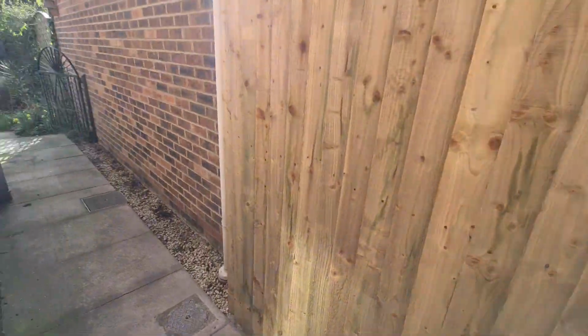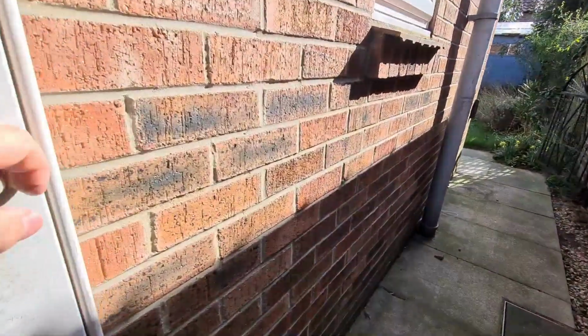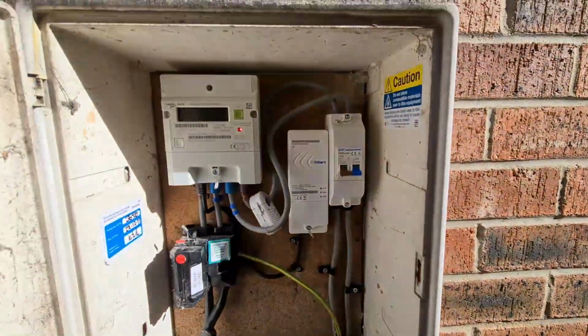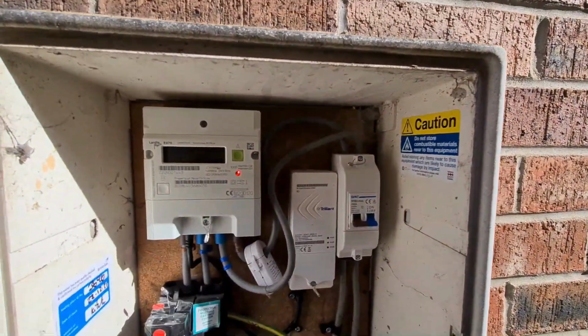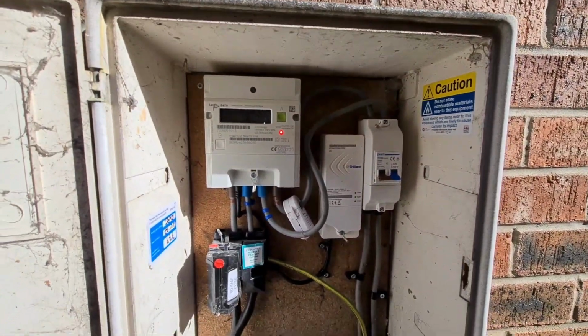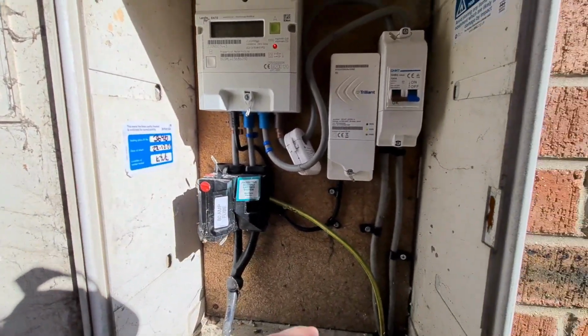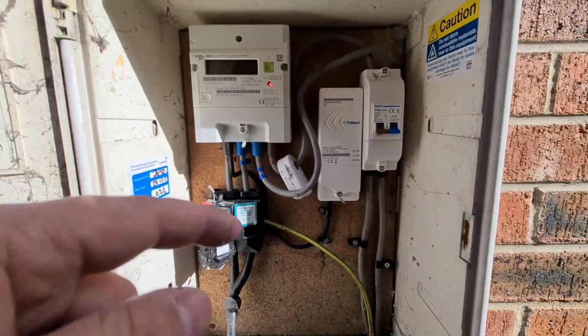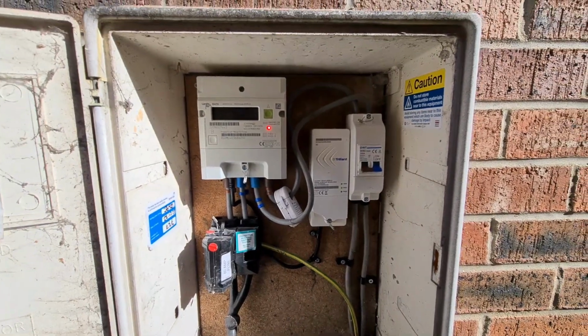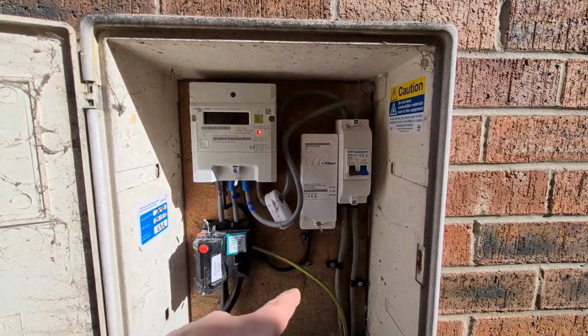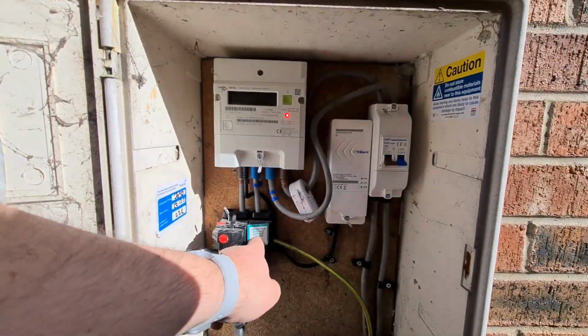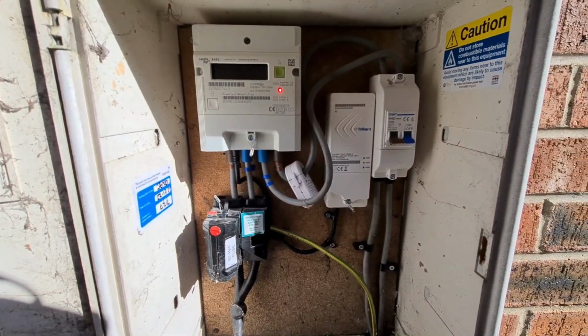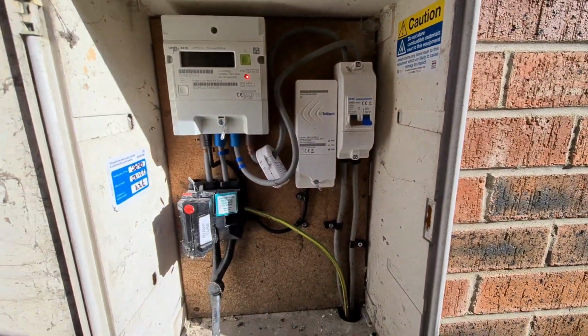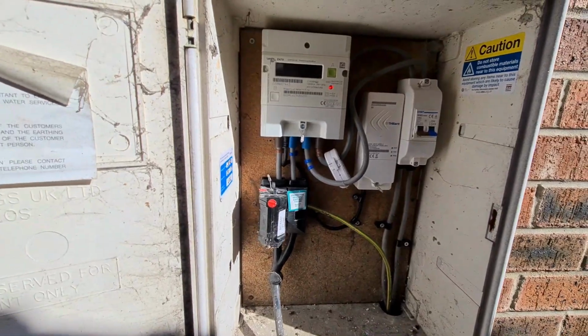So we'll start off outside. Outside we've got the meter box, and you'll see we've got a nice main isolator. I'm going to get that locked off so we can work quite safely. 80 amp fuse coming in. We've got our earthing conductor as well, so we can do a few little tests out here, make sure we haven't got any leakage currents floating around the earthing system because it is a PME. We'll get this locked off, and then we know we're perfectly safe inside, and we'll carry on with the video.